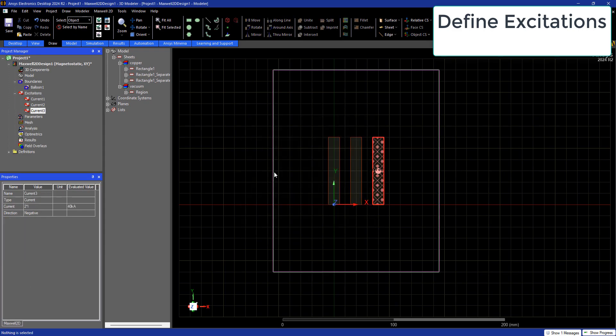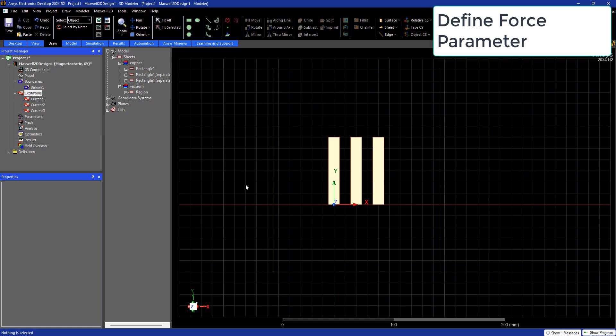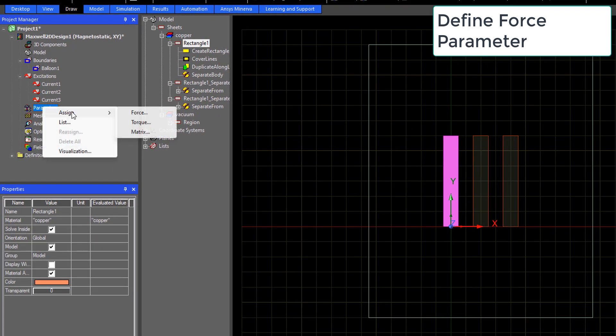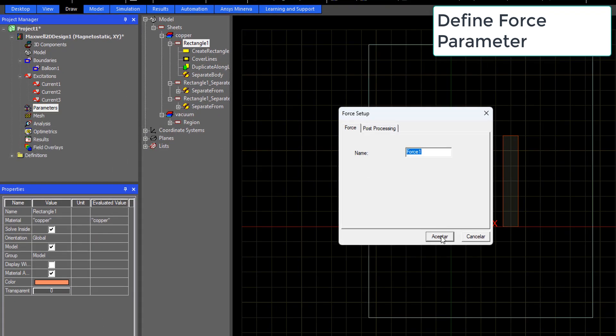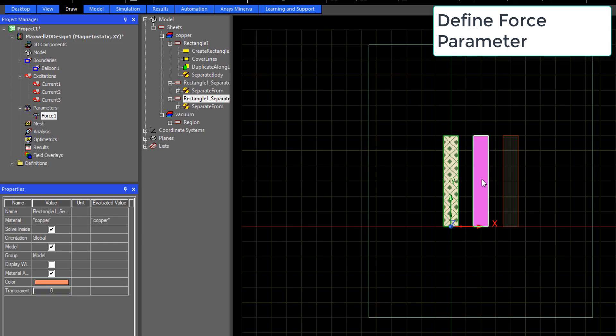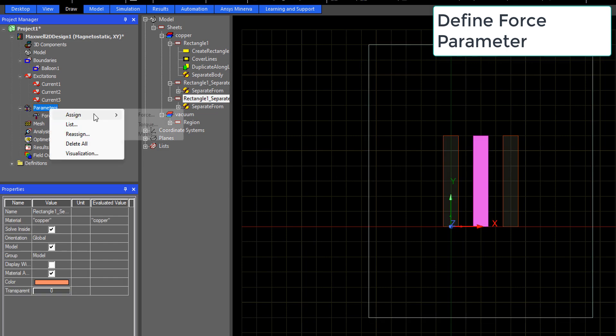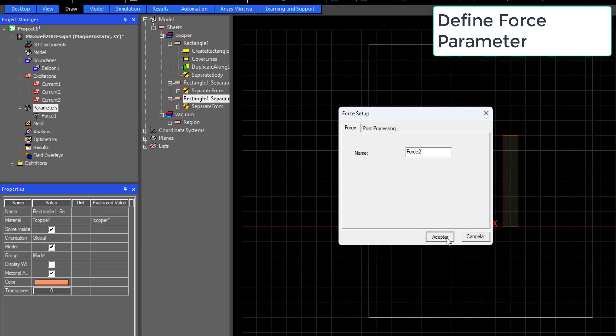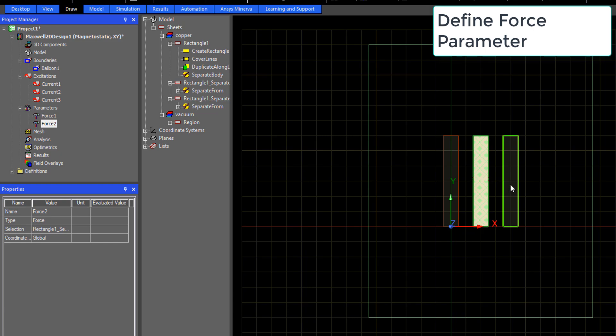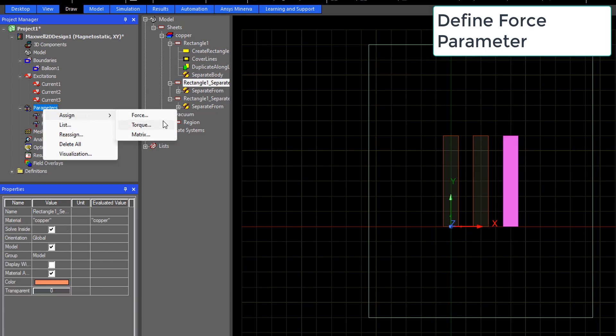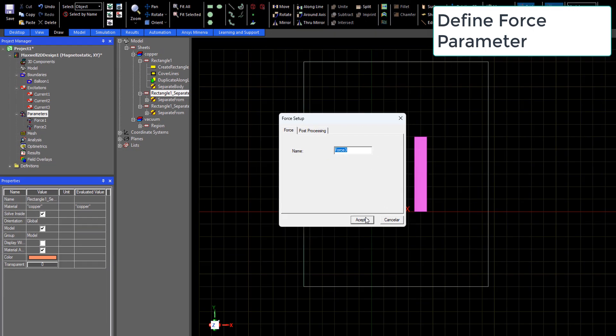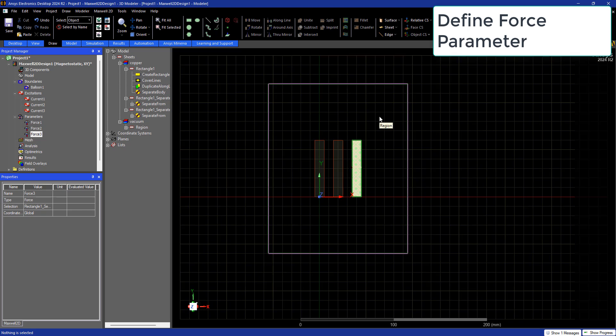Now let's go ahead and define a force parameter. You need to make sure not to select all the busbars at once, otherwise you will get the total force of the system. You need to apply the force parameter to each of the busbars individually.